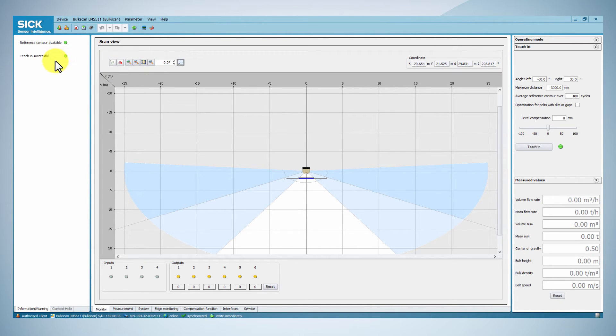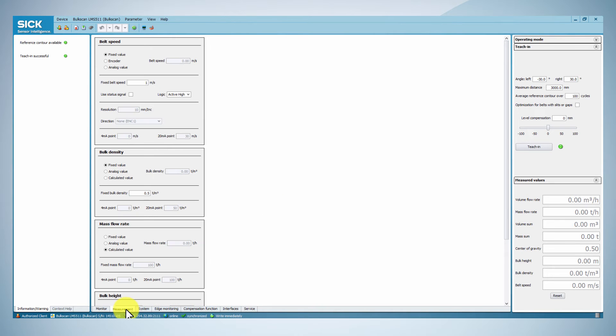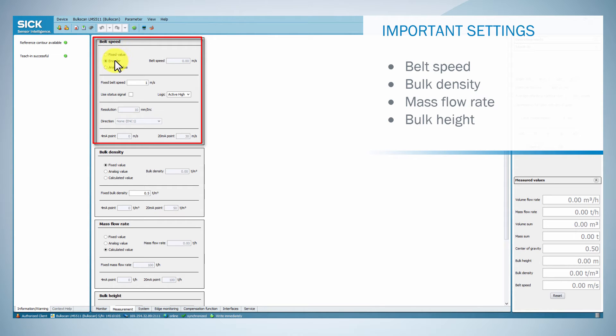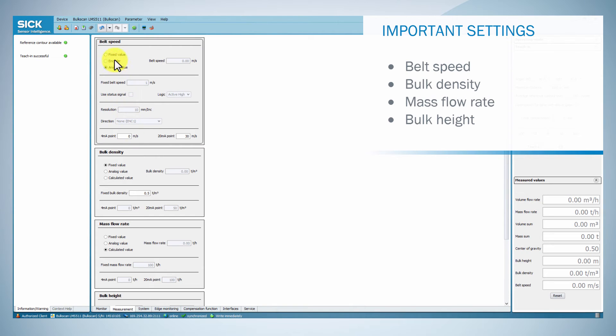In the measurement tab, you can select a source for the conveyor belt speed. It is possible to use a fixed belt speed value, to use an incremental encoder, or to input an analog current signal using the BAM 100 analog module.